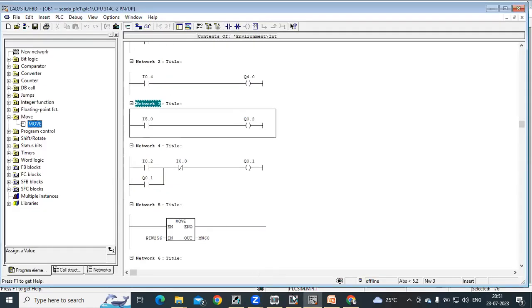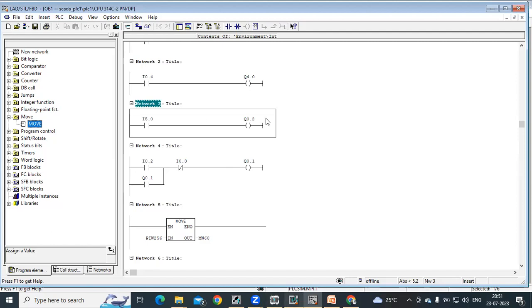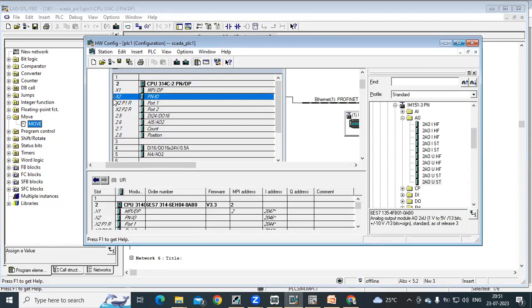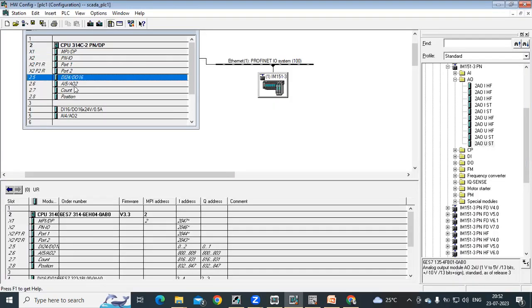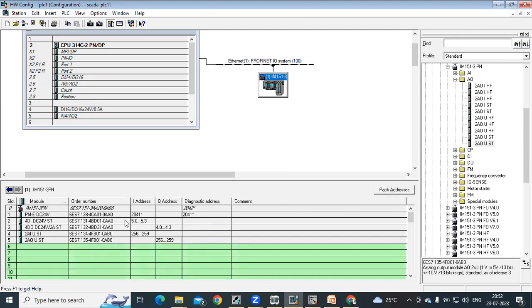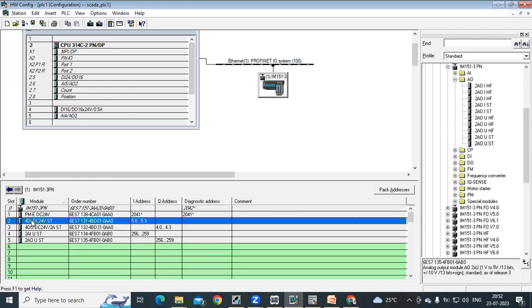You can check the address in here. For the local IOs, the byte number starting 0, byte numbers are starting from 0 for inputs and outputs. Whereas, when you select this IM, it is starting from 5 and 4. 5 for this input, there are only 4DI, so byte number 5 with bit number 0 to byte number 5.3.